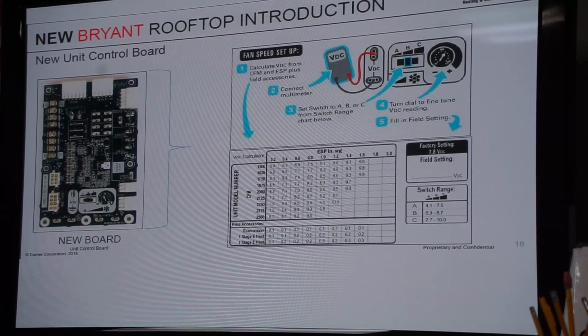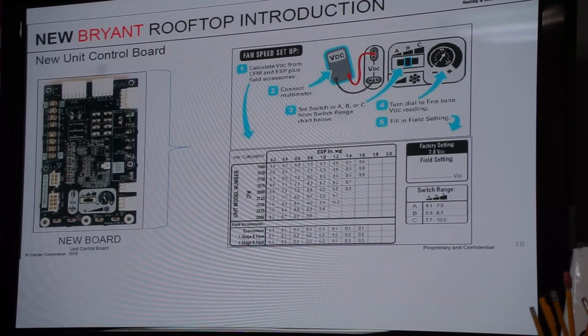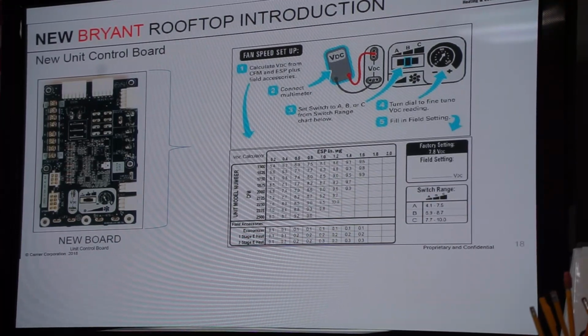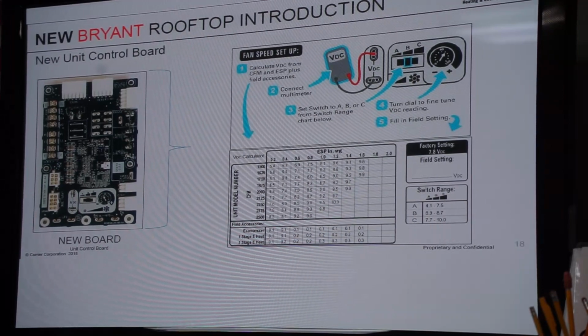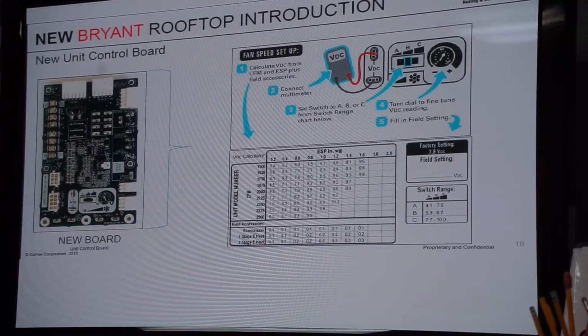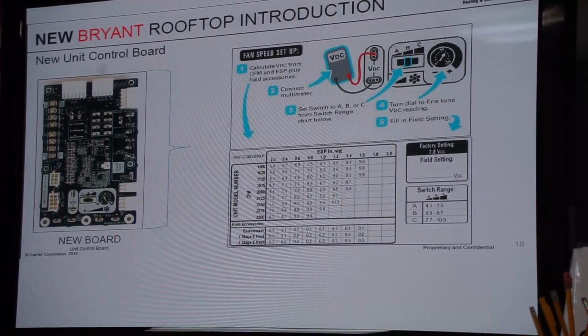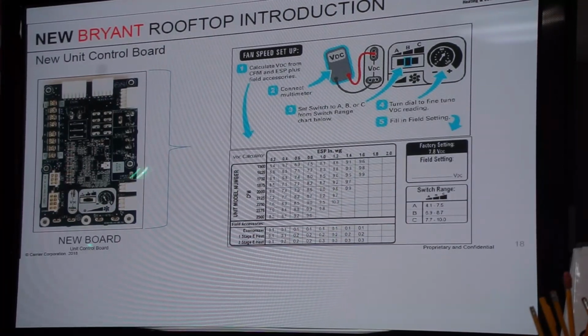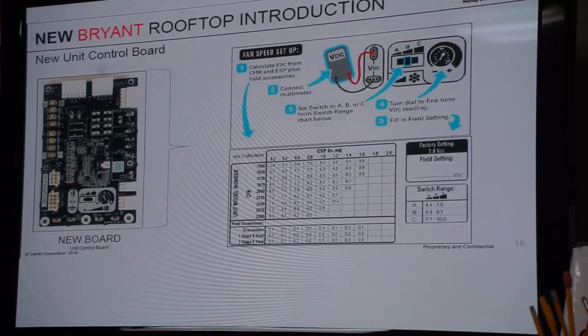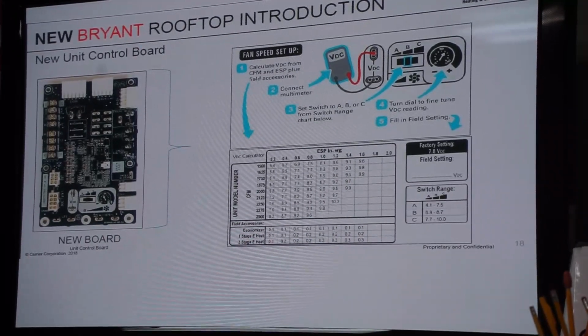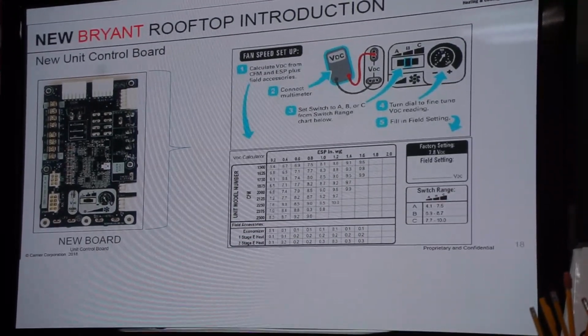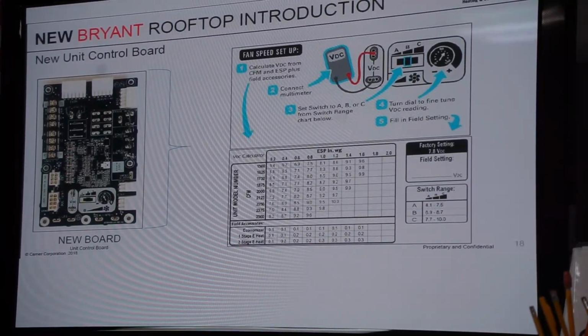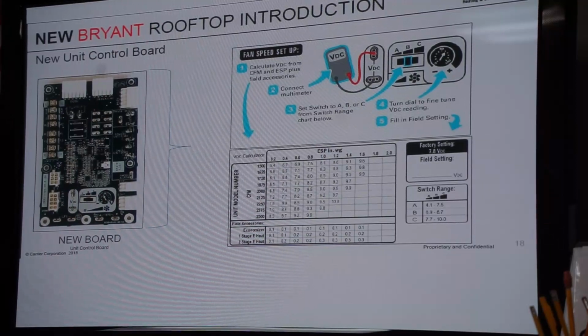Troubleshooting. We've got a video on troubleshooting this that I'm going to go over real quick. But the mindset: do I have 10 volts coming from that motor to here? So I'm going to put my meter right here. Do I have 10 volts there? Do I have 8.7 going out? If I don't have 10 volts, what's my problem? Motor. Something's wrong with that ECM. It's not serviceable. You're ordering a new motor. If I've got 10 volts, but I don't have 8.7 going out, it's my board.